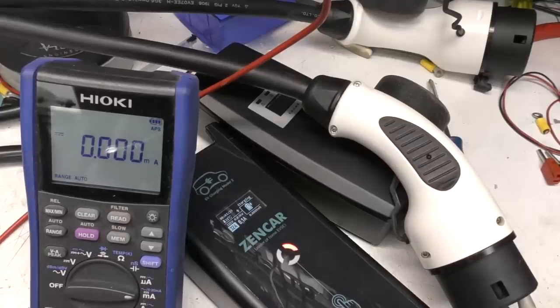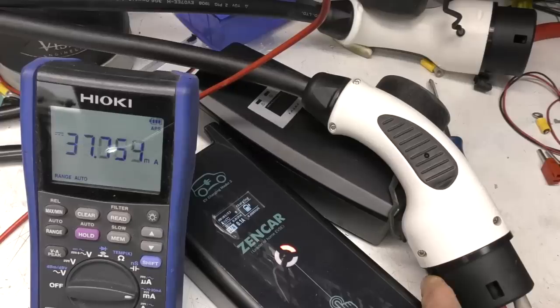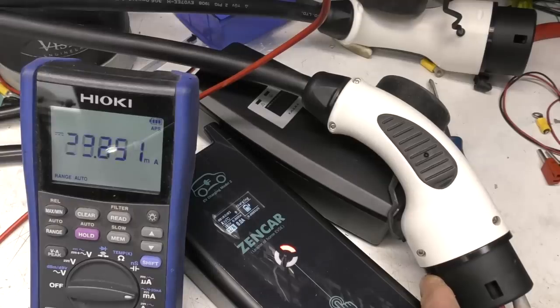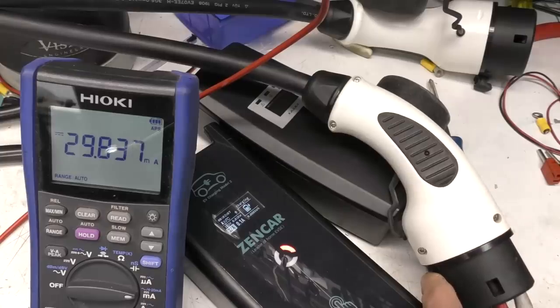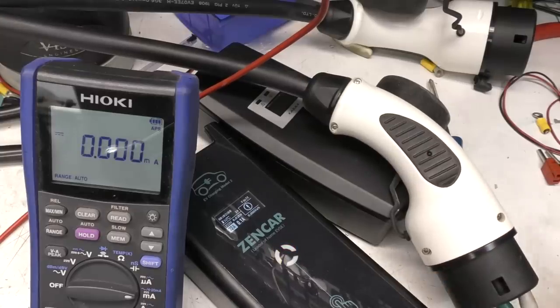Okay, let's see if these have got any sensitivity to DC faults. What I've done is I've just got a DC bench supply and a series resistor that I'm going to connect across between the input neutral and output neutral to produce some DC current through its current transformer. Increasing, 50 milliamps, and no trip up to over 100 milliamps. A sudden DC fault will generally produce a trip because of the AC component.